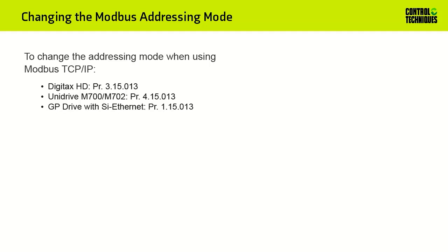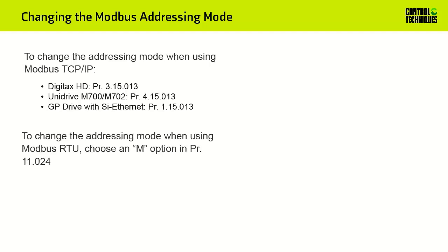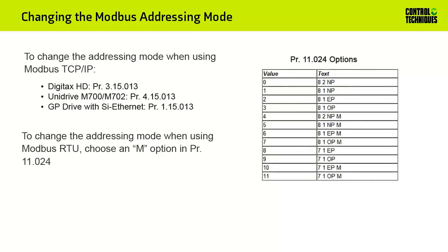In a Unidrive M700 or Unidrive M702, this parameter is found in slot 4, menu 15. In a general-purpose drive that is equipped with an SI Ethernet module, the addressing mode parameter is found in slot 1, menu 15, parameter 13. The addressing mode may also be changed when using Modbus RTU. To do that, refer to menu 11, parameter 24.